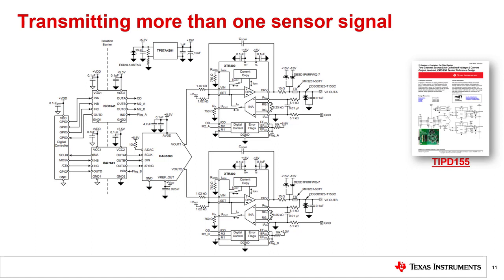Unlike two-wire transmitters, where the I-return pins float and need to be independent from each other, three-wire transmitters can share their grounds with other three-wire transmitters without any input isolation. The reference design is linked to this slide and offers a full design walkthrough including part selection, simulations, and design layout.